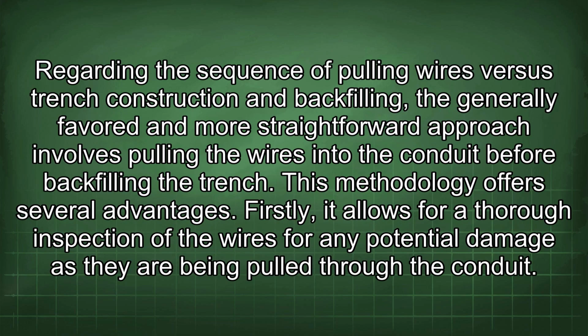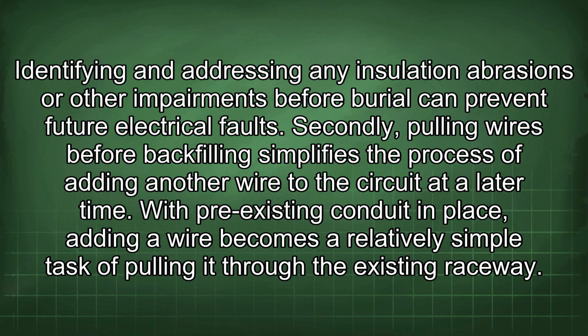Regarding the sequence of pulling wires versus trench construction and backfilling, the generally favored and more straightforward approach involves pulling the wires into the conduit before backfilling the trench. This methodology offers several advantages. Firstly, it allows for a thorough inspection of the wires for any potential damage as they are being pulled through the conduit. Identifying and addressing any insulation abrasions or other impairments before burial can prevent future electrical faults. Secondly, pulling wires before backfilling simplifies the process of adding another wire to the circuit at a later time.